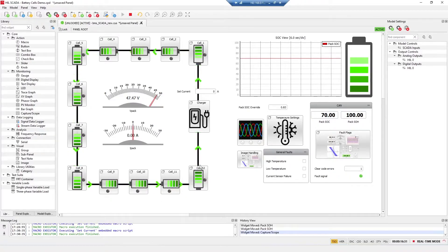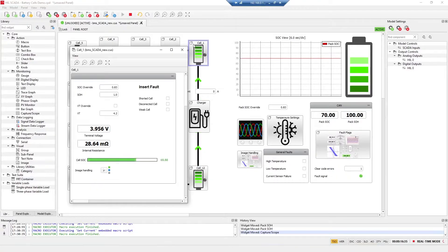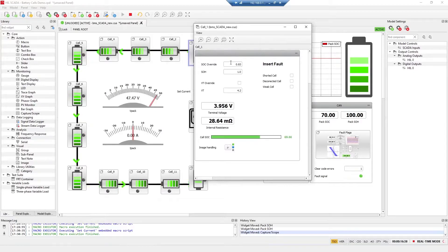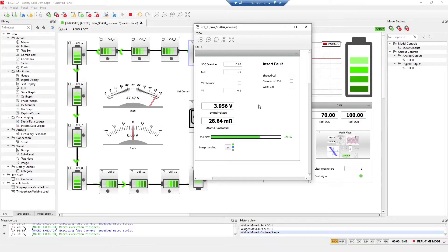Here are all 12 battery cells. For each cell you can override state of charge, state of health, and voltage, and you can monitor terminal voltage, internal resistance, and cell state of charge. Also for each cell you can insert a fault such as a shorted cell, disconnected cell, and weak cell.